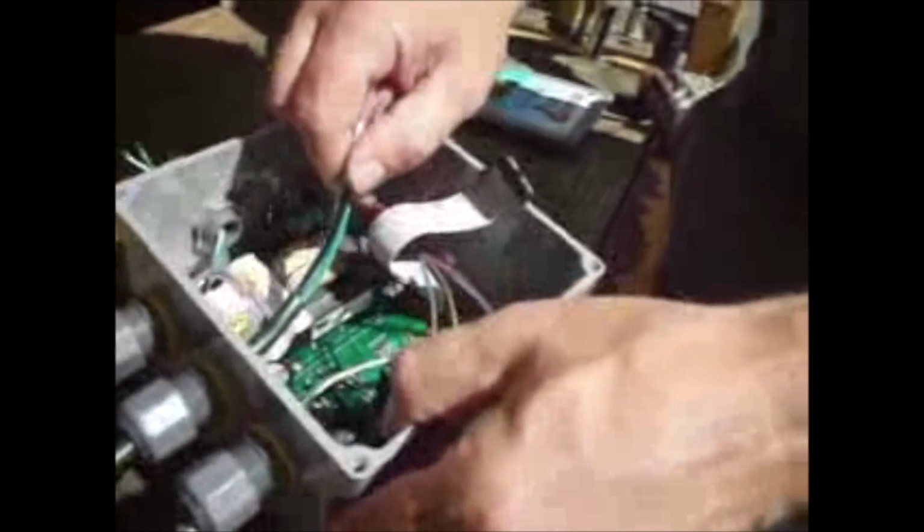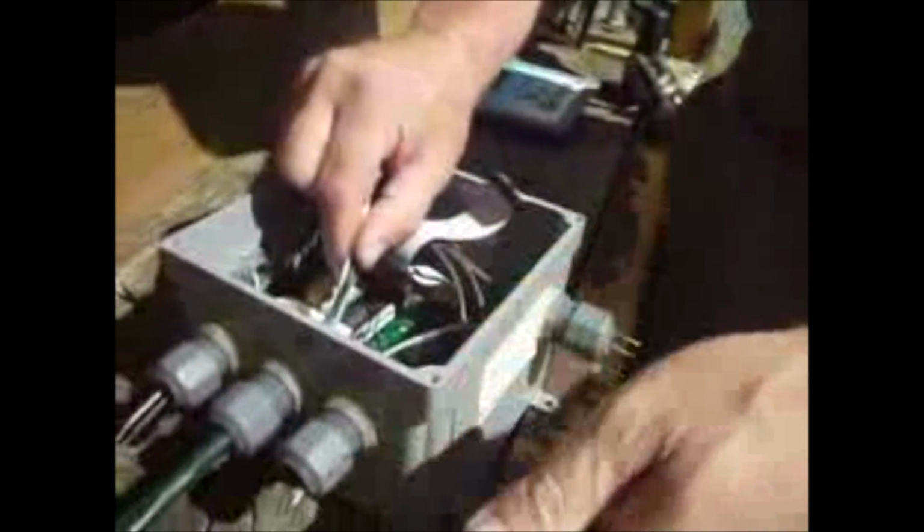Alright, so I want to show how you actually use a strain relief and how they work. So in here is a rubber gasket that there's a tapered area there. Then when this gets tightened, it squeezes that gasket around the wire. So the strain relief is very loose. This wire has already been stripped. Push it through the strain relief. I like to get to the point where the insulation is just showing on the inside of the box. And then you tighten the strain relief. And now that cord is attached.